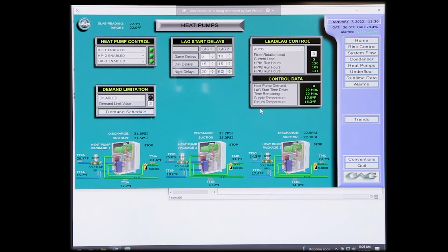Okay? And this is just another graphic reread of all the different sensors we have. These are individual cold sensors that are on each of the individual chillers here. Your in and out temperatures. You also have in and out temperatures on your glycol, on the warm glycol leaving this specific chiller. You have suction and discharge readings also. Here's where you'll see a start command when it calls to start, and then you're going to see anti-cycle come on, okay? And it'll have a timer underneath here. We do not allow that compressor to restart again within that 20 minutes, and you'll see that here. So to see anti-cycle is a normal thing.